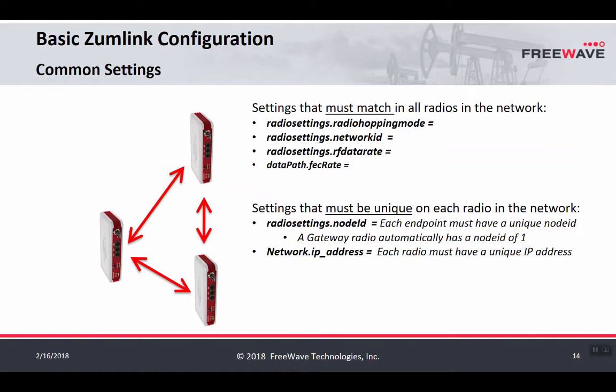In contrast to the common settings, there are also settings on a Zumlink radio that must be unique for each radio in the network. The first is the node ID, which helps the network organize itself and understand each radio's position by a numerical system. In a hopping mode network with an established gateway, that gateway will always default to a node ID of 1. All node IDs must be unique, and a good system to keep them separate is to use the last three digits of the IP address as the node ID. Zumlink being an Ethernet device also must have a unique IP address.